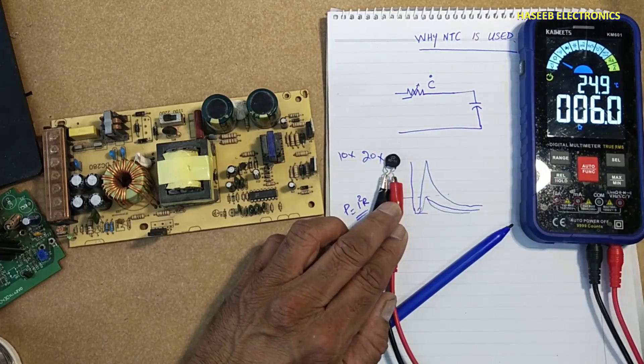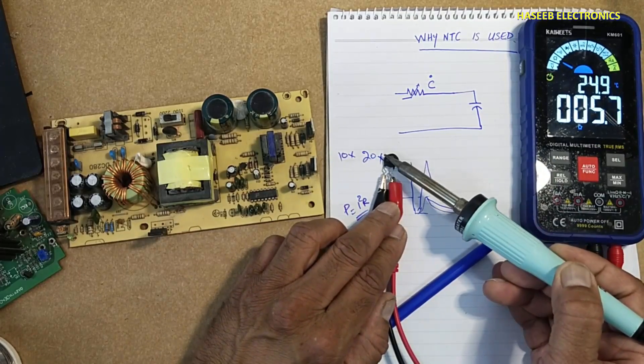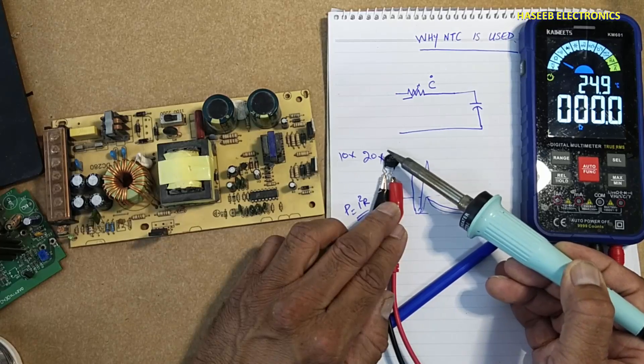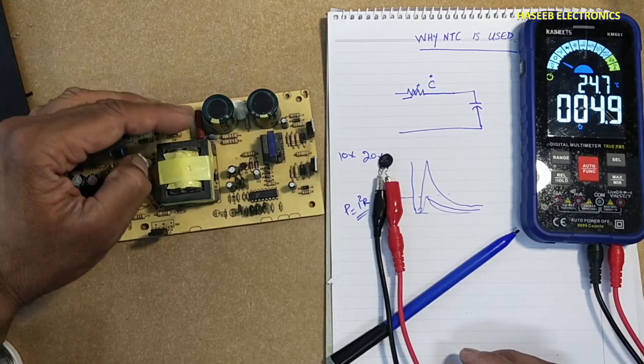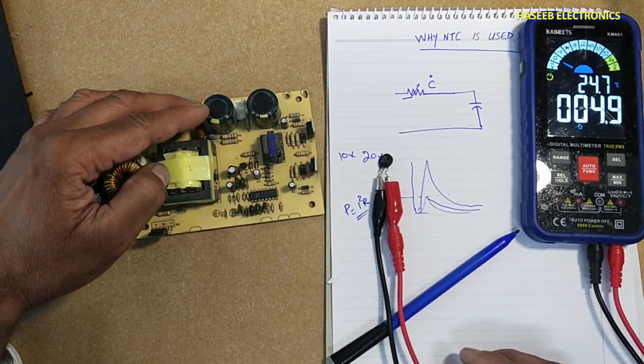Normally it is 5 ohms. When it is heated up, we can see its resistance is dropped, so it will protect the system from drawing high current while charging process of these capacitors.